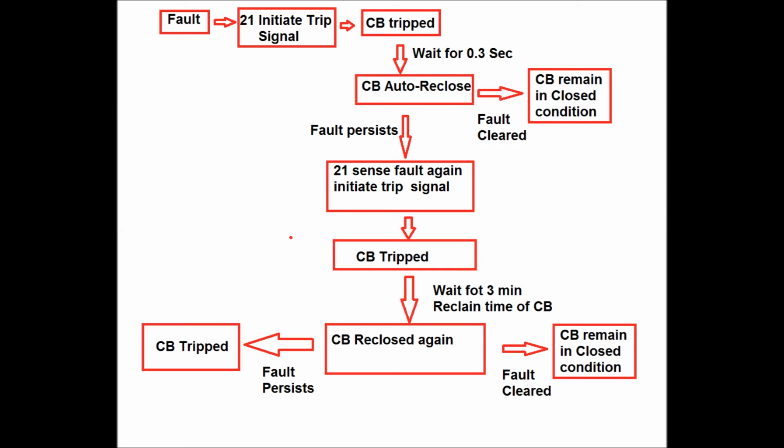And this auto reclosing duty or operating cycle is recommended by the manufacturer of the circuit breaker. If the second reclose shot is given within 3 minutes, then it will affect the life of the circuit breaker.